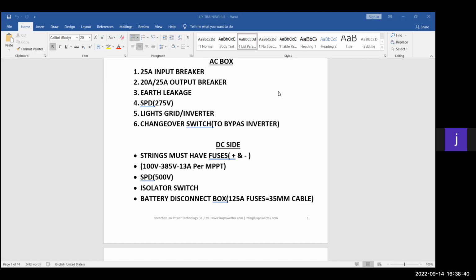We won't tell you your breakers were the problem on a warranty claim or so forth. We just go on the data that the inverter showed me. So I only put this recommendation there to try to protect everything on the machine. Clients don't always look at the amount of power that they are pulling. Clients get very comfortable with machines. There's no load shedding, they don't check the schedule anymore, and before they know it, they put on a few things and then they trip the inverters and stuff like that.